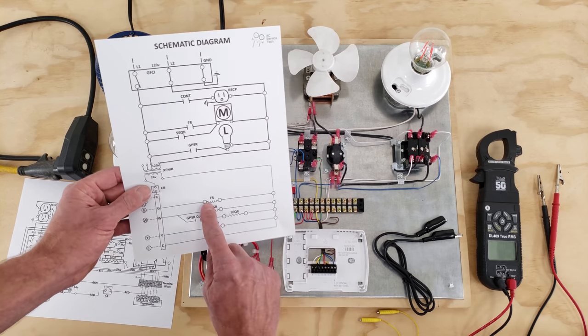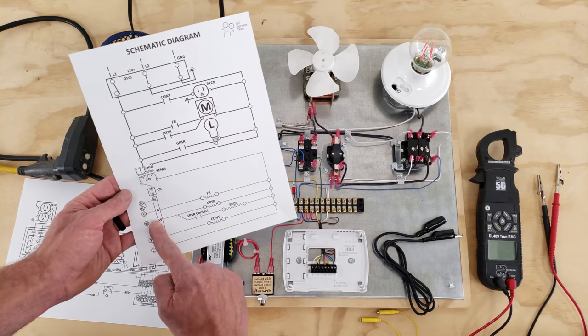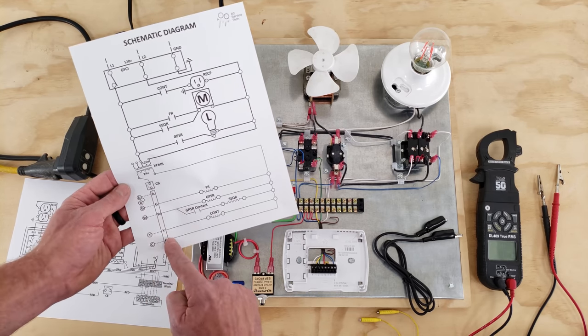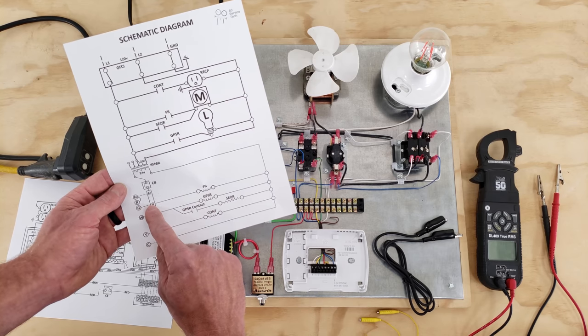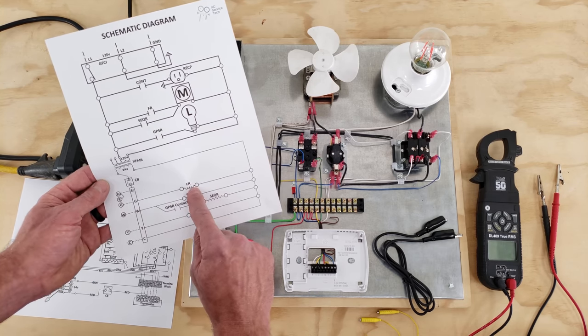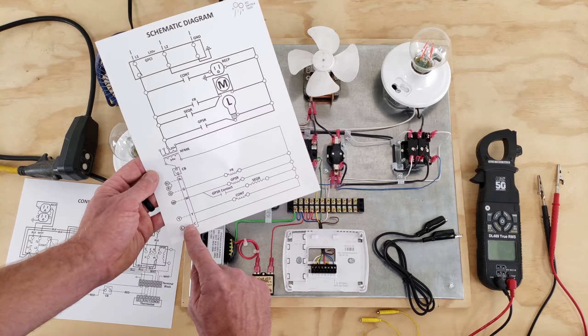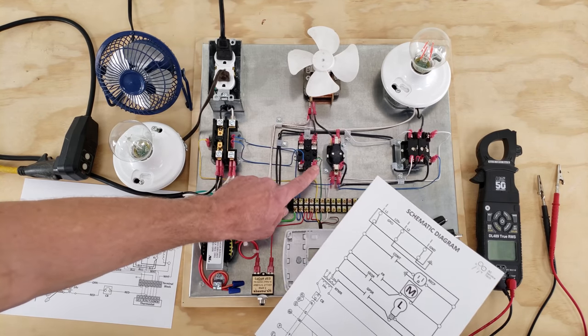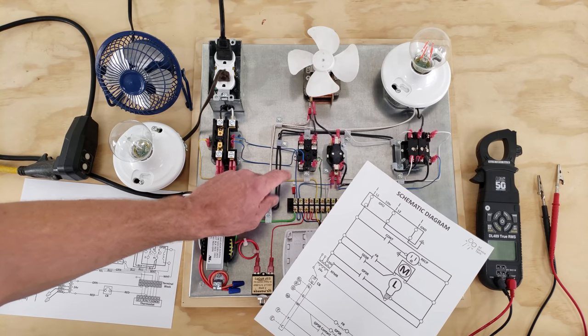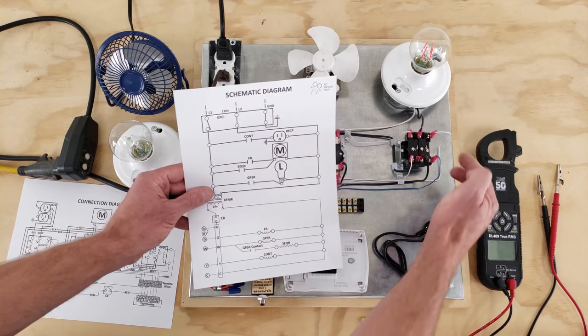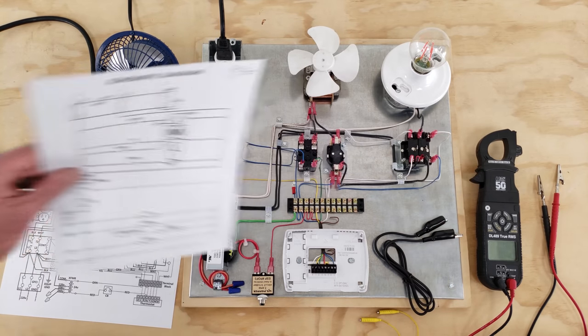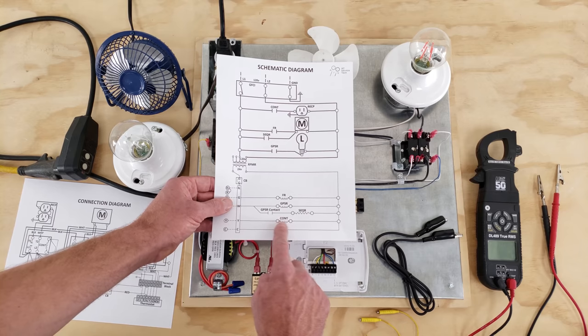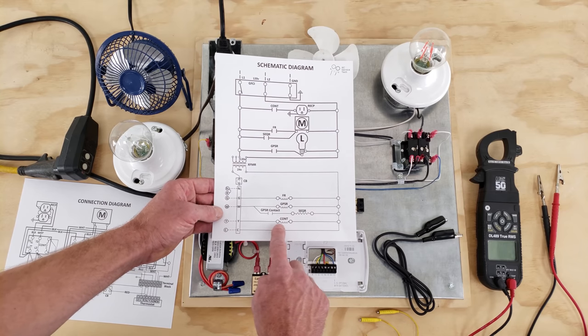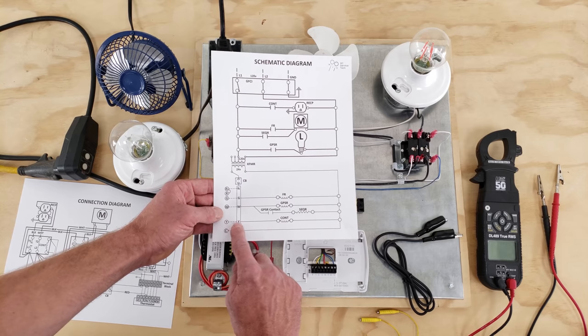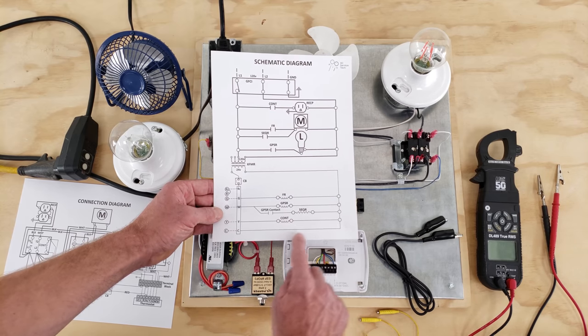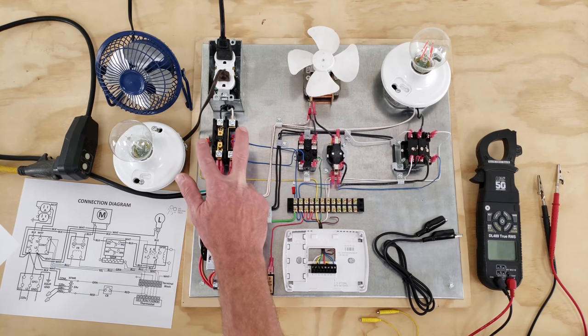And so you can see your fan relay coil. So you have your thermostat right here, is your thermostat connections, here's your terminal block, and then basically you have your G going over to your fan relay, and then it's connected to your common right here. This is your fan relay coil, and here's your common. Your GPSR coil, that's located over in the lower section of this coil right here. Here you have your cont, so that's your contactor, and there's another coil right there. So you see your Y connects to one side of the contactor coil, and then you have your common wire on the other side. And so there it is right there.